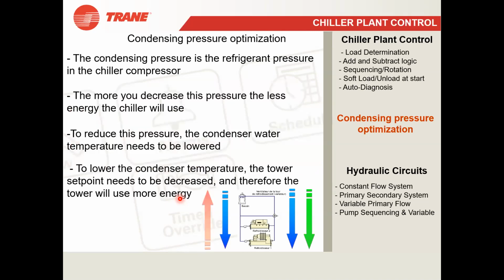So it will actually set accordingly. It is not that you have decreased the set point at the cooling tower, so the cooling tower will now be working at full load or maybe a higher load, and then you will be getting a huge electricity bill. It is not like that, because you are reducing here also. The chiller uses less energy here because you are reducing the pressure. So actually it is a combination and mixture of both.